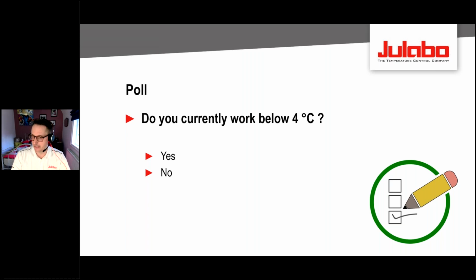So that's a really good hint to ask yourself: do you really, really need to go below 4 degrees C? Going back to what we need to measure, assuming you're running tap water at the moment, you can measure the temperature of tap water very easily. You can measure the temperature of the water after your condenser when using your rotary evaporator, so you can determine a delta T. The next thing you need to measure is the flow rate through your system.